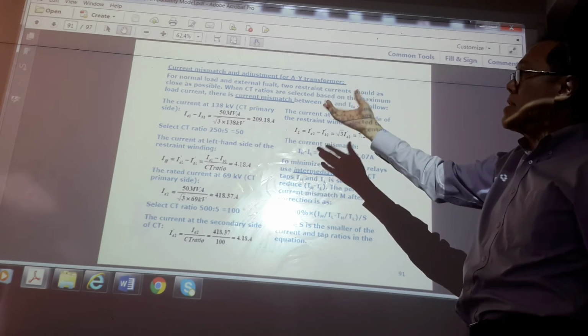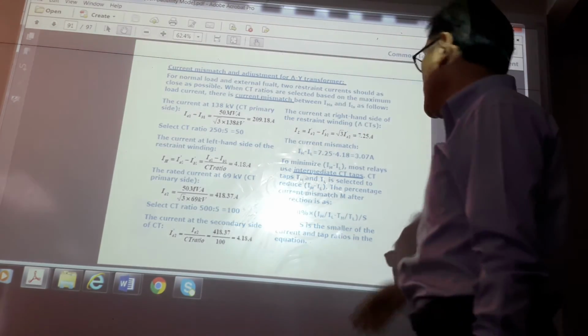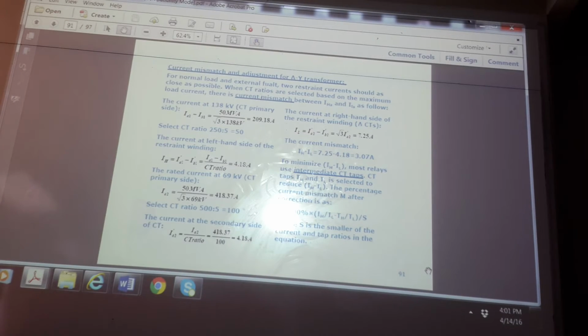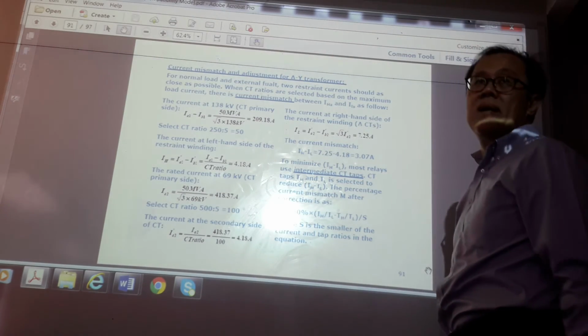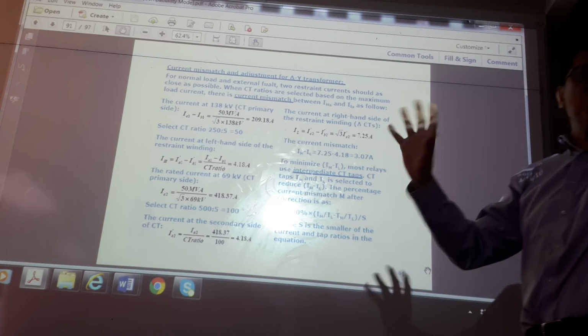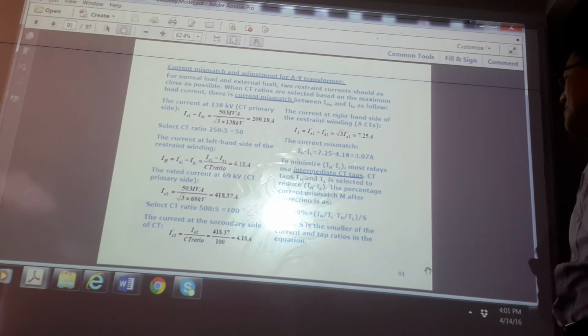I think this problem actually introduced a tap for you, kind of 9 and 6. So we have to use on the high voltage side the value of 6, low voltage side 9. So that means you use 6, 9. Right? This is a tap 6 and 9. 6, 9 means 2/3, 0.6667.